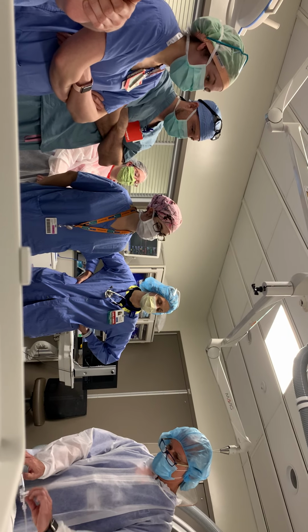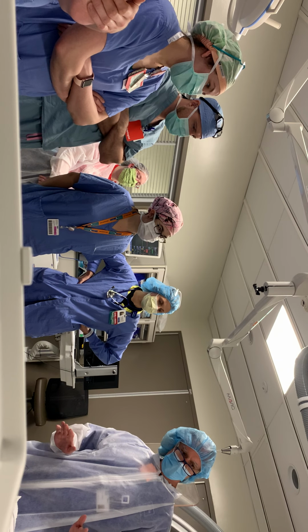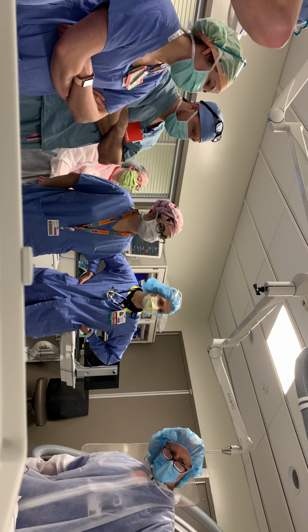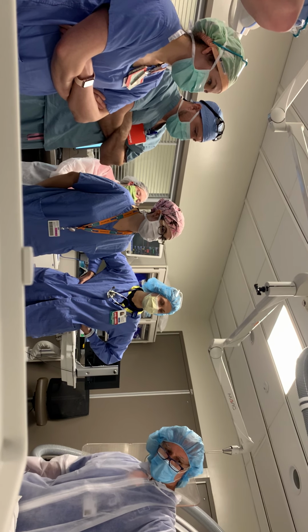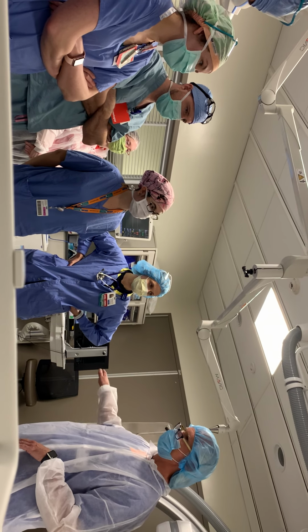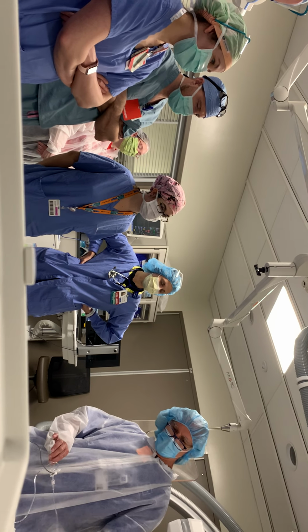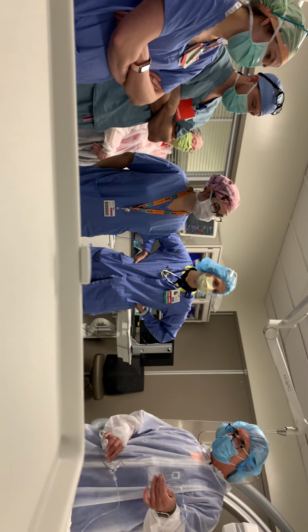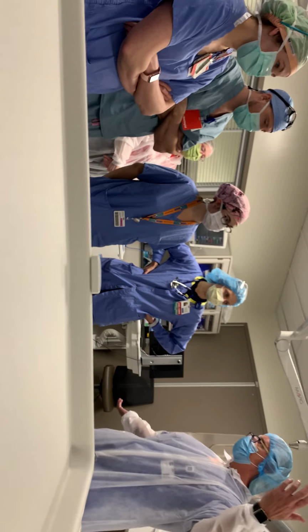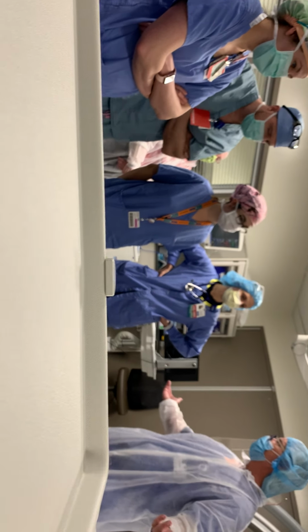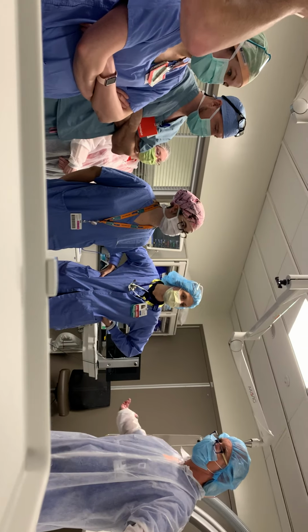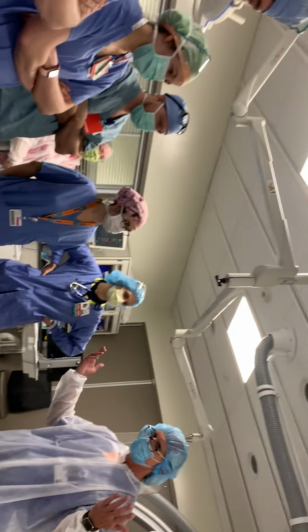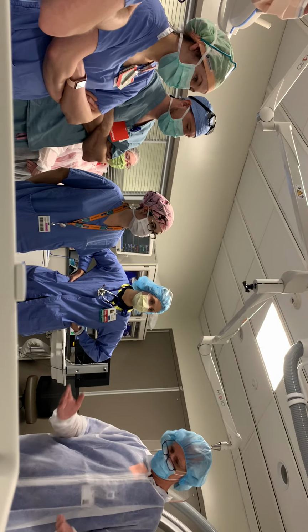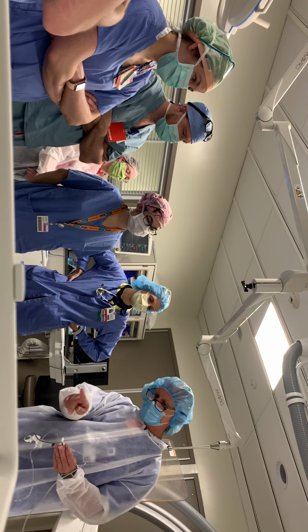Whenever you're talking about a counterbalance with transducers, you simply are counterbalancing the weight of the fluid at that end to heart level, so that the weight of the fluid that's in the catheter and this line just cancels each other out. That's it. It's an algebraic equation. Once you do to one side, you do to the other, cancels out, and it's meaningless. What's left is the patient's actual pressure. So you have flushed that line.